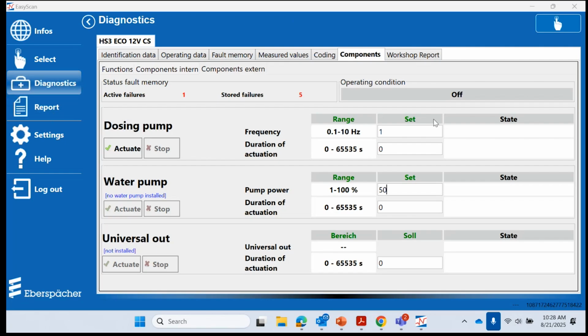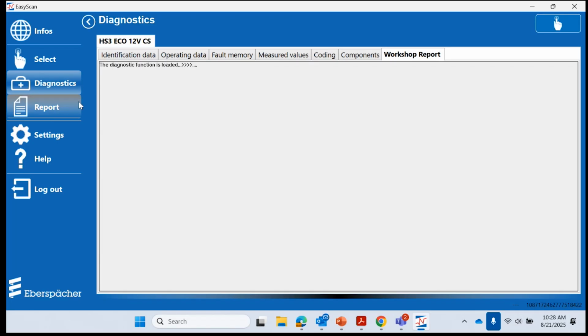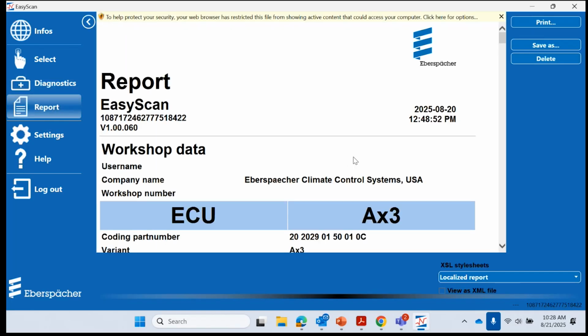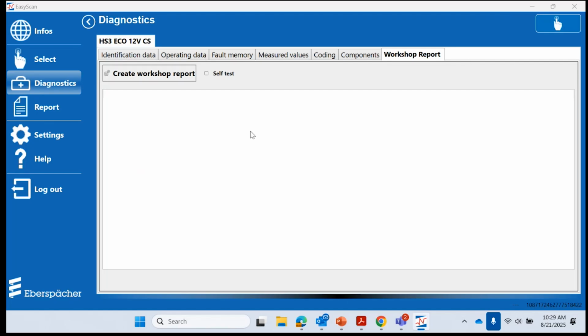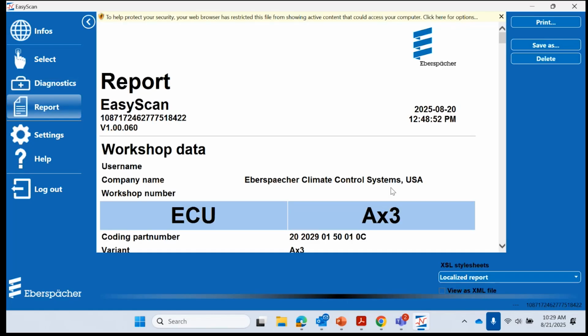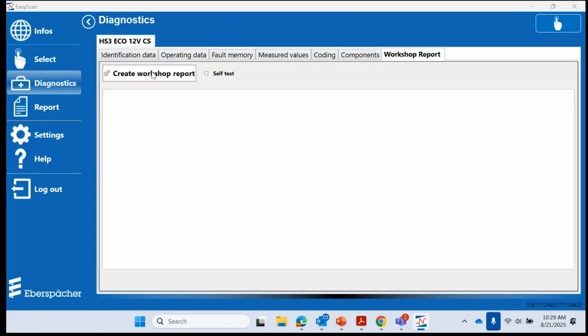Now, at the end of the day, when you're doing this diagnostic test, you can also create a workshop report. So if you click on report in the main menu, it'll show us a report that was created on the 20th. That's yesterday. But then you can go in over here and create a report. And then when you do that, your existing report will be overwritten. Now, ideally, you'll have to delete it rather than override it. That's the recommendation. Right now, I'm not going to do this because I would need this file. So I'm going to save this file first, and only then I can do it. But you get the idea. You have to delete the existing reports, go into diagnostics, click on workshop report, and create a brand new workshop report. That's the way it should be done.